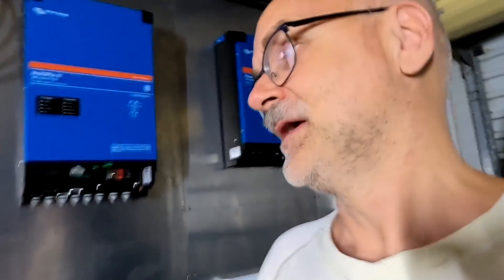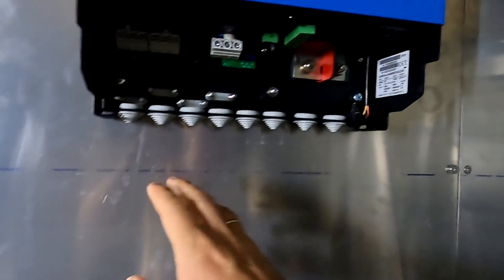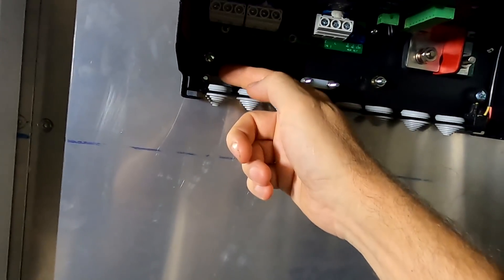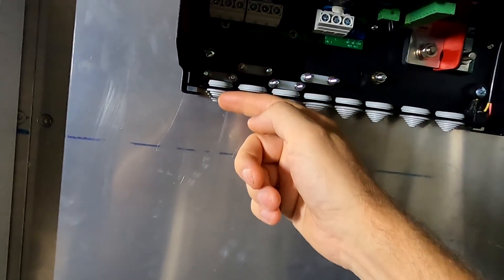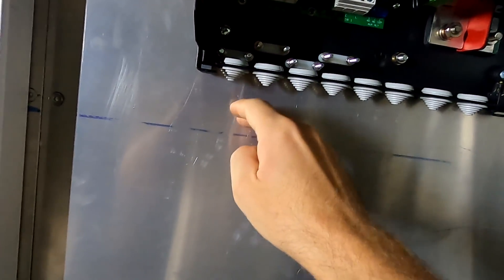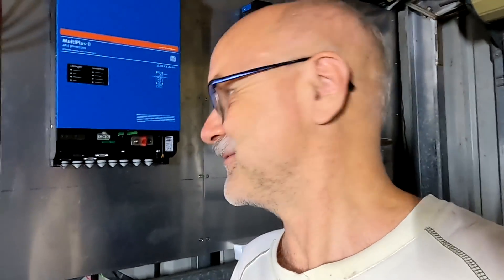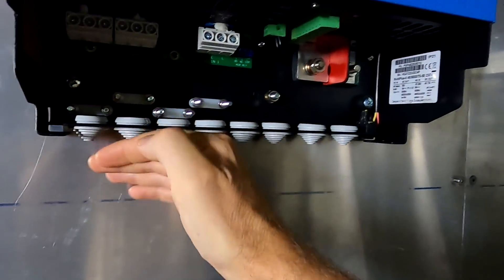So obviously I have to go with solution C, but I decided to go with a very unpopular solution A. So we will cut holes in the aluminum sheet here and then put all the cables from here and conduit going down behind. I'm just kidding, guys. I'm just kidding. We are not going to drill or punch or saw or cut any holes in this aluminum sheet here anymore. We've done this before and well, it didn't work. Once the cable is in this corrugated conduit, you will never get it out again because these bends are so sharp.